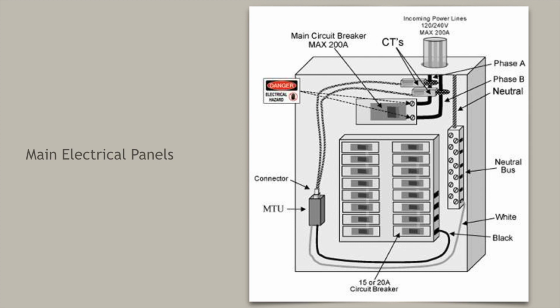The service entrance wire terminates at the main panel. The purpose of the main panel is to protect the branch circuits from an overload. It may look like a distribution point, but in reality, it is a fire prevention device. The house is broken down into multiple circuits or branches. Some of the branches handle electrical equipment like dryers and stoves that need a large amount of current. Those circuits require wires that are rated large enough to handle the higher loads. For example, 8 or 10 gauge wire. Other circuits are only connected to outlets, switches, or lights, and they only require a 12 or 14 gauge wire.